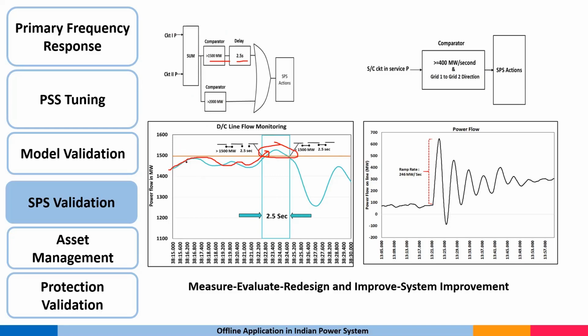But we have the megawatt information at our end also with the help of PMU, and it is dynamic. You have to check whether the condition holds for 2.5 seconds, so you need very good data; the resolution should be quite high. We see that for 2.5 seconds, the power is above this 1500 megawatt, so the operation was correct. Another SPS was checking whether the rate of change of power is more than 400 megawatt per second from this side to this side, not from this to this side. What we observed is that it was operating irrespective of the direction. So we blocked this SPS based on the information collected from the synchrophasor data itself.